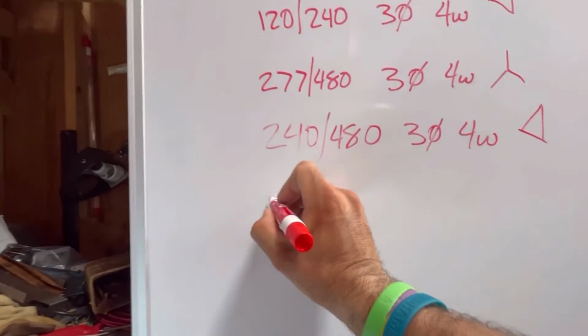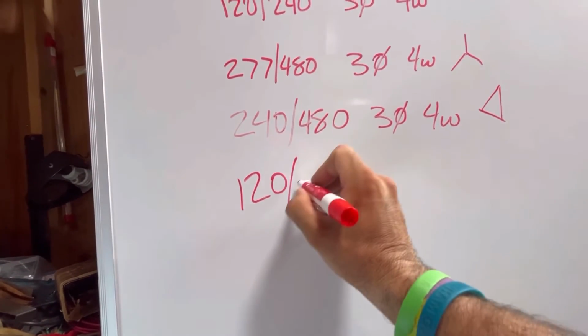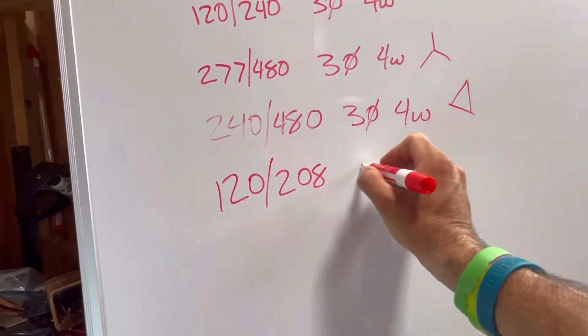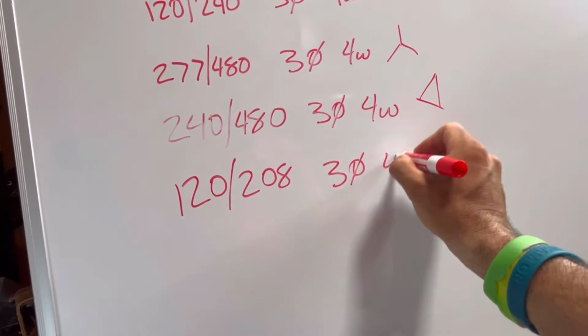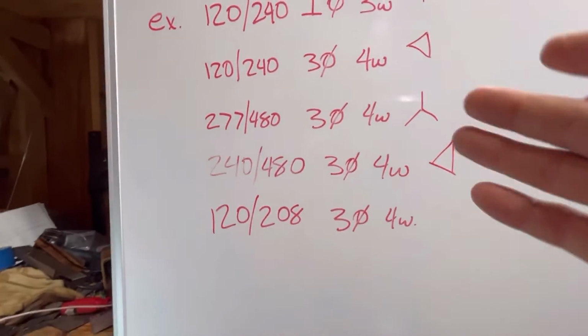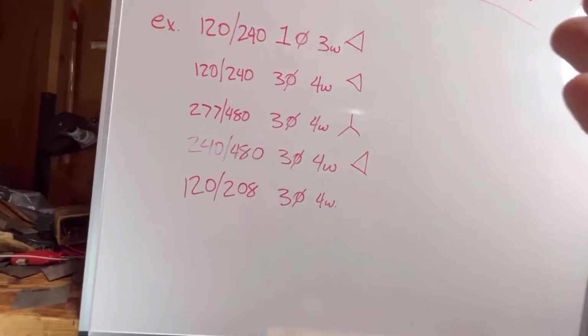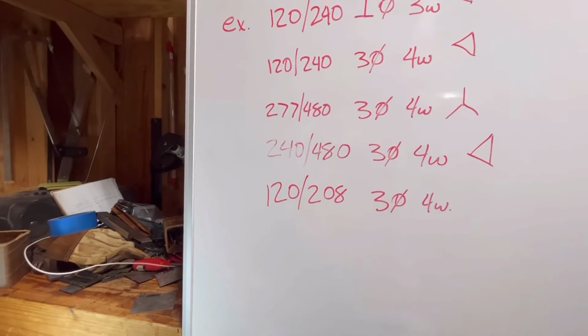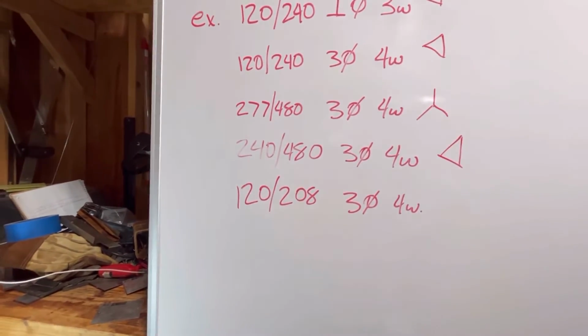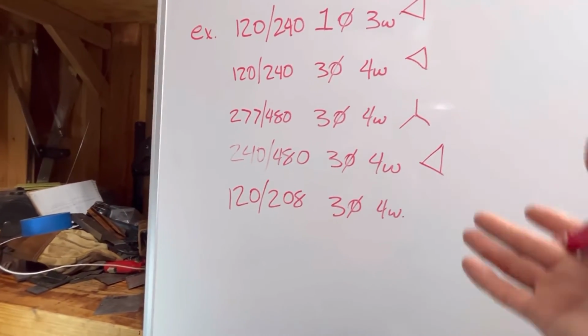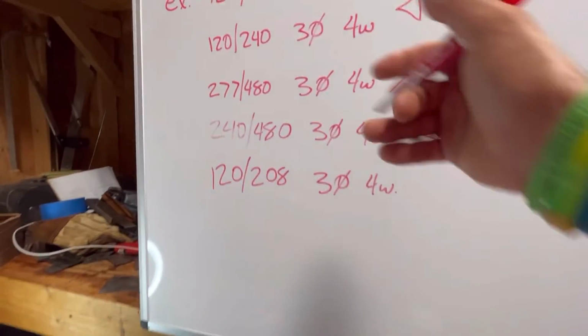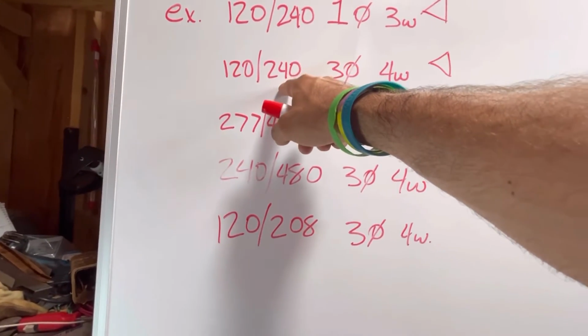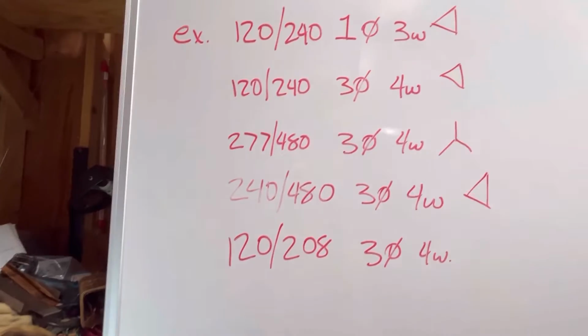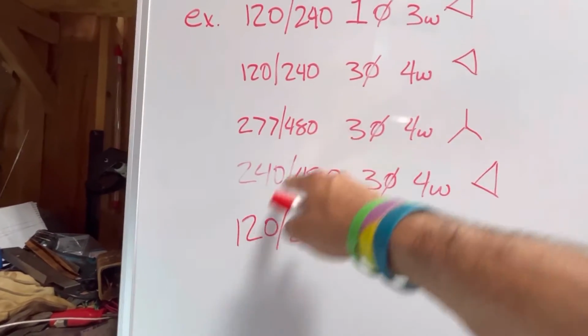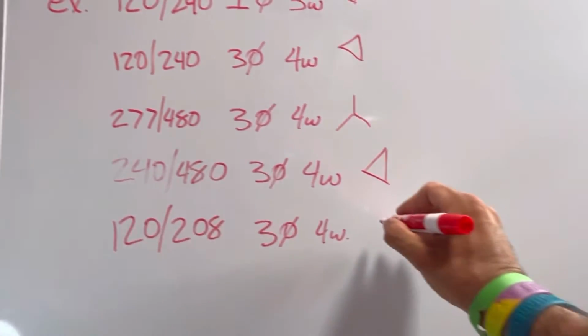And finally, 120/208, three-phase, four-wire. And guys, I apologize. I know there's a ton of different voltages around the world. Europe uses some pretty crazy high stuff, so there's a ton of them out there, but the same rules apply. Delta divide. If your voltages divide evenly into each other, it's going to be a delta. If they don't, it's going to be a Y.